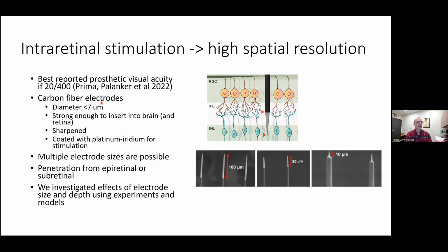So carbon fiber electrodes are a technical approach to that, and that's what's shown in both this diagram and these electron micrographs here. This is something one of my colleagues at Michigan, Dr. Cindy Chestek, has advanced for neural recording. And then we deposit on our platinum iridium material. I also want to disclose I have a commercial interest in platinum iridium, so I'll talk about that a bit in the next few slides. This is because carbon itself is not robust for long-term electrical stimulation. As you can see, we have a few design choices we can achieve with carbon fiber electrodes, including something as small as 10 microns, though the robustness of this is somewhat questionable if you try and insert something with a small tip like this.